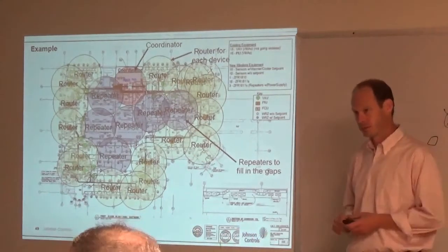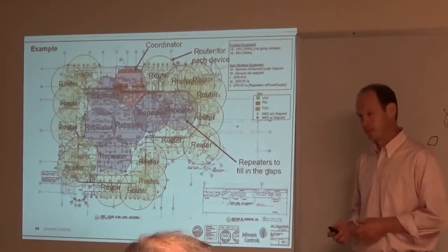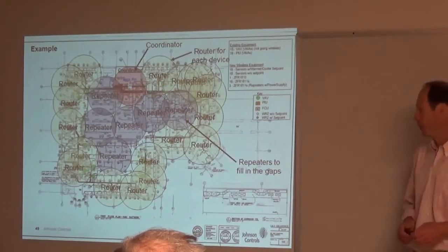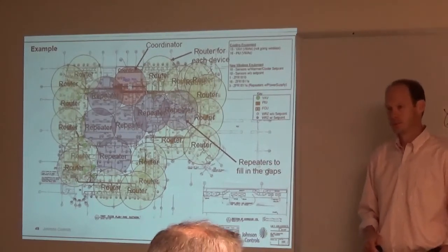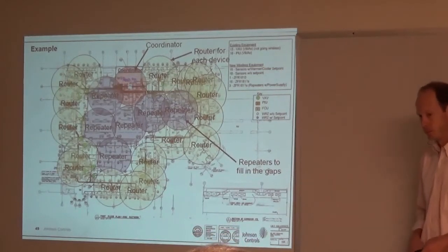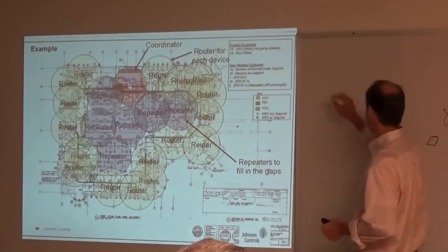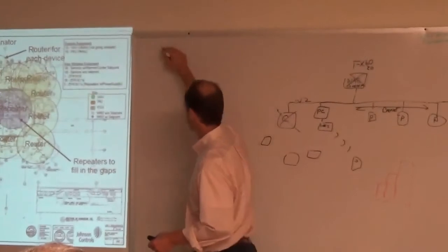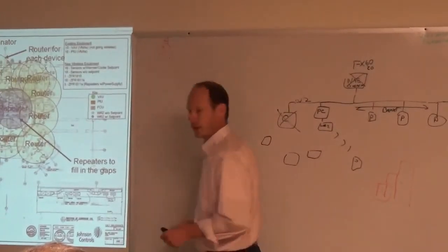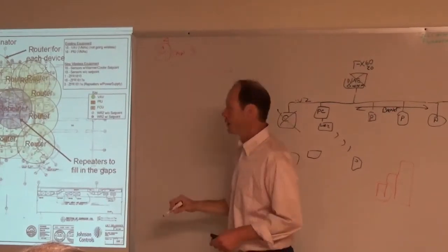Can the sensor and the controller be on separate PANs? No. Because if you had a three-story atrium, with the VAV box up on the third floor and the sensor down here in the lobby, you've got a problem. What you could do is this. Let's say this is floor 3, floor 2, floor 1, and the controller is up here with my flag in it. This is personal area network, PAN number 3, and that's set by the flag.